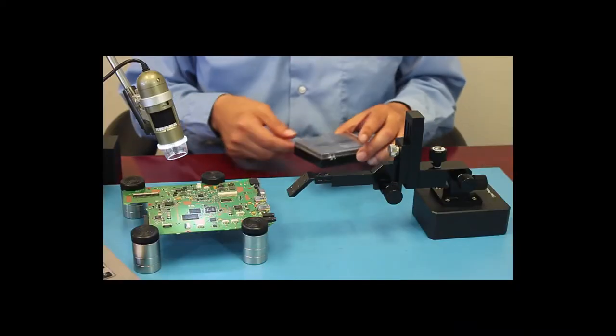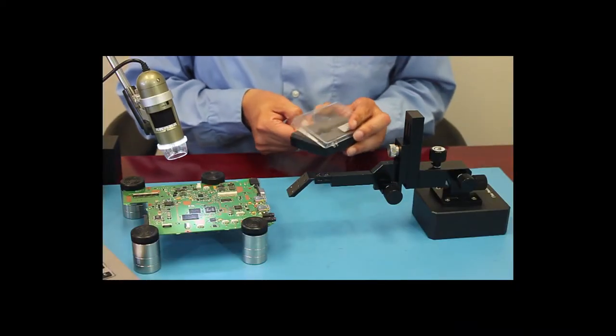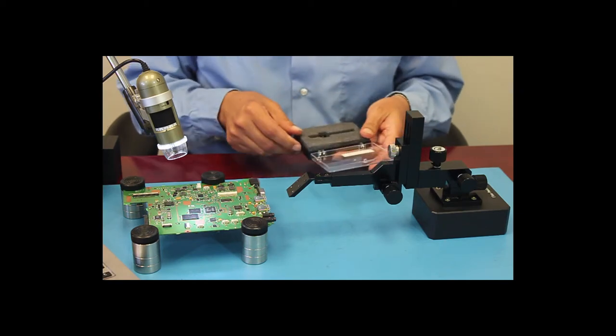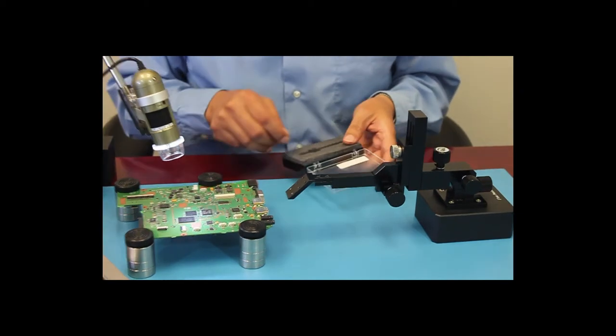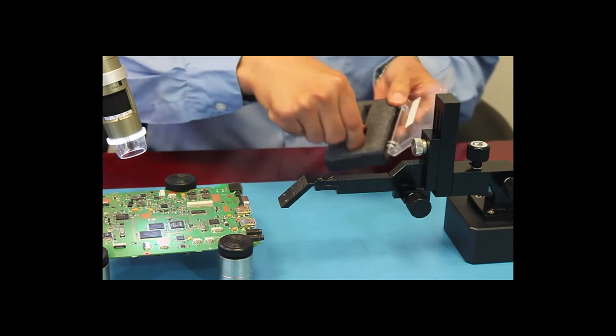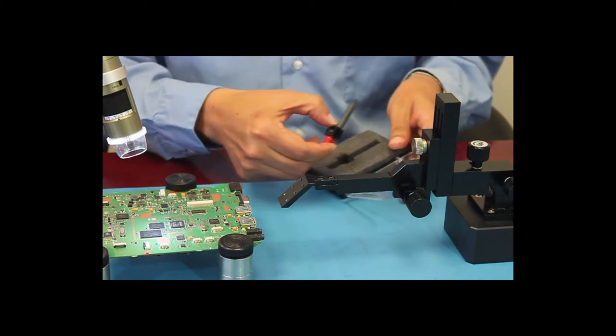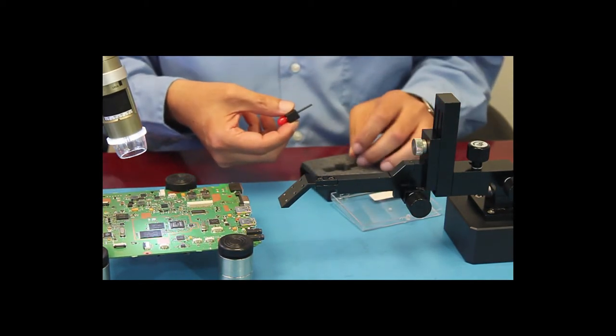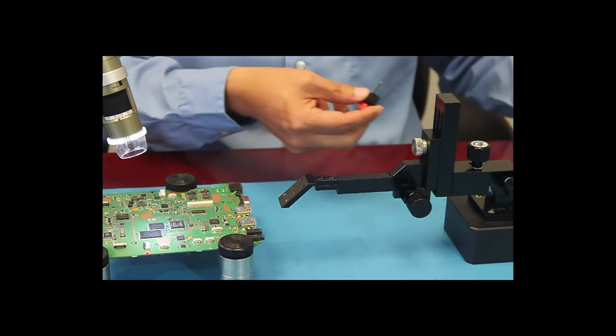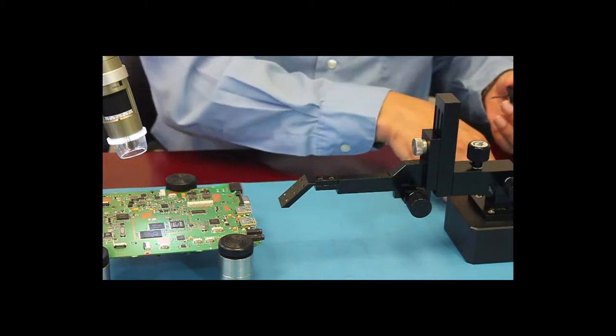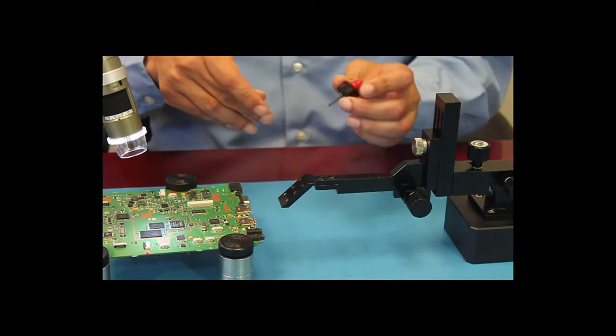Now that you have an idea of the features of the TB60, let's start probing. We'll be using a small PCB board for today's example. However, any size board can be used. Let's take the R probe out of the box and put the provided two screws into the R probe while using the two millimeter hex key to secure it onto the probe adapter.